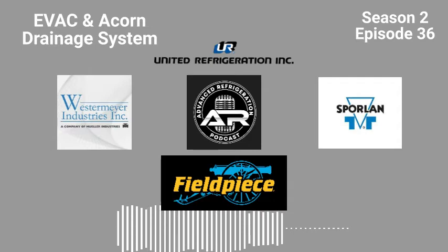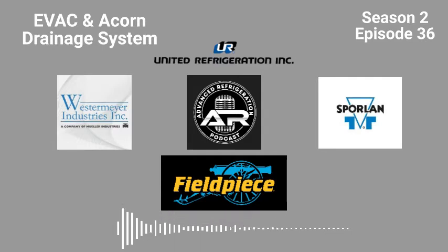That sounds disgusting. So the other thing, guys, to watch out for is vacuum loss. Say you come to a store and you have water literally everywhere and the vacuum pumps are just running nonstop. Generally, what I will do is I will just start listening for the whistle. In one of these cases, you're going to hear it. You're going to hear the pinch valve up in the ceiling, or it's going to be sucking all the time down by the floor. Go ahead, Brett.